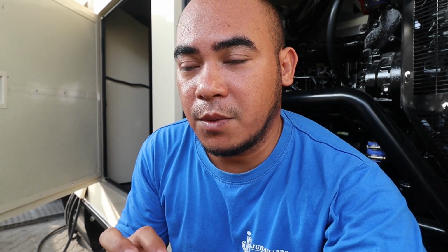So now I'm finished writing the configuration, so I will double check again our AVR adjustments and AVR wiring, everything. Okay, we're done with the configurations for our COMAP module. So we also need to configure our ECM in order to communicate on the CAN bus. This is important, because if you do not do the configurations for this one, it will not make the bias for your speed.